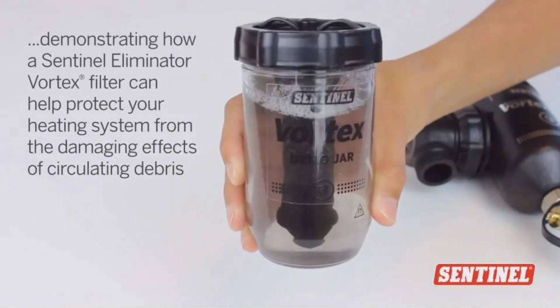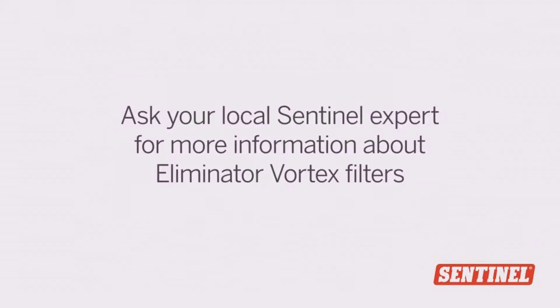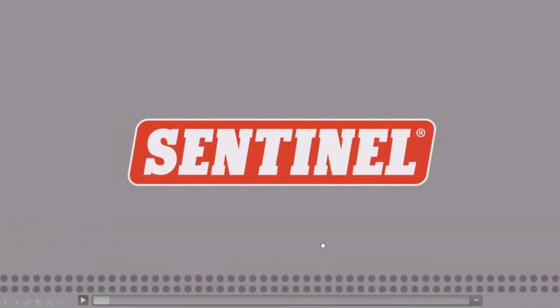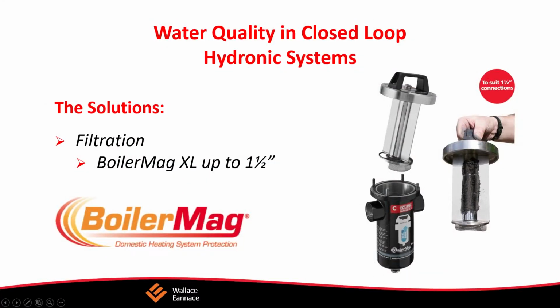We had the clean, which was the 800 for older systems or the 300 for newer systems. Then we have the protect, which is the 100, and then the test kit level is for maintain. This is the maintain section. The test kit is a simple device where you just take a small sample, dip these strips in there, and they tell you whether or not you have the proper protection. These little strips will give you the right answers. So it checks the inhibitor level in a minute.